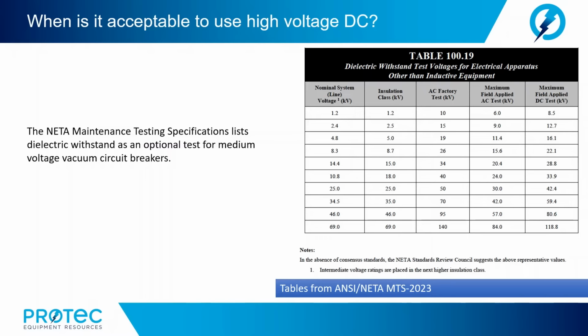Okay, now the NETA maintenance testing specification lists dielectric withstand as an optional test for medium voltage vacuum circuit breakers. And both AC and DC voltage values are given in the reference table 100.19, the dielectric withstand test voltage for electrical apparatus other than inductive equipment. So here we do see that we can use DC as an option.